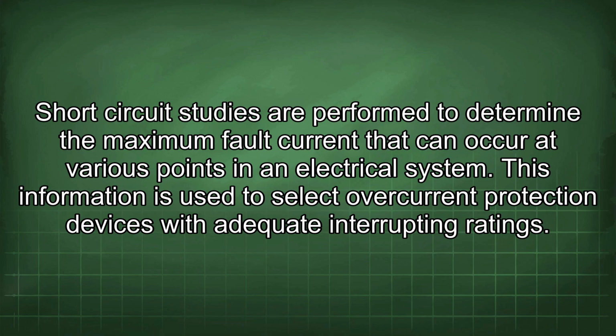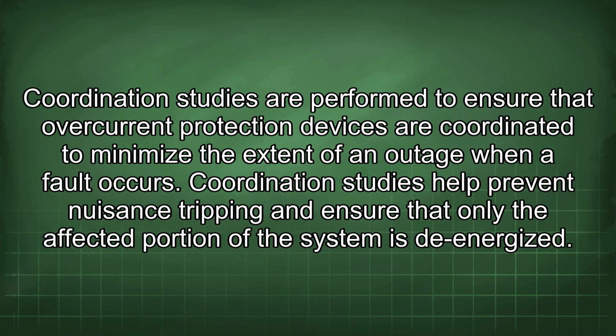Short circuit studies are performed to determine the maximum fault current that can occur at various points in an electrical system. This information is used to select overcurrent protection devices with adequate interrupting ratings. Coordination studies are performed to ensure that overcurrent protection devices are coordinated to minimize the extent of an outage when a fault occurs. Coordination studies help prevent nuisance tripping and ensure that only the affected portion of the system is de-energized.